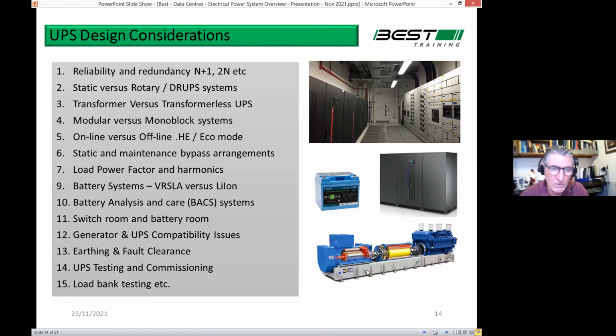In a diesel rotary system, which is called a DRUPS, diesel rotary UPS system, that's what you see there on the bottom diagram. So it's a generator at one end, a diesel generator, just as we saw in the last diagram. And then you have a flywheel. Now, I'm not going to get into explaining how this works. It's a very, very complex piece of machinery, but it's basically a kinetic energy store. There are 2 rotors, one rotating at 1500 RPM, and an outer one running at 3000 RPM.